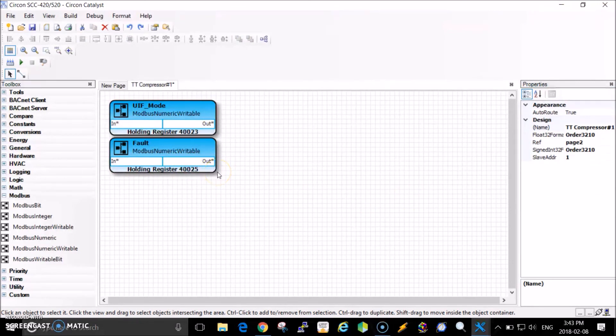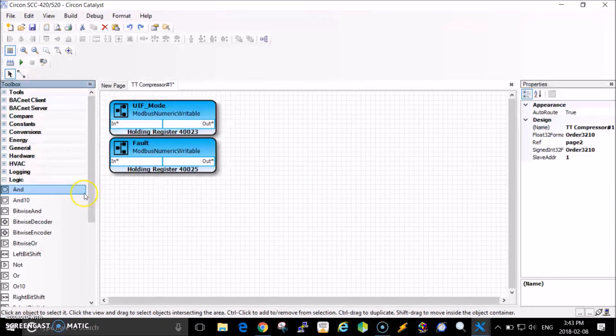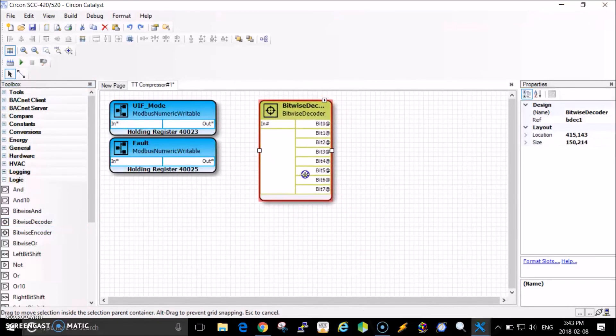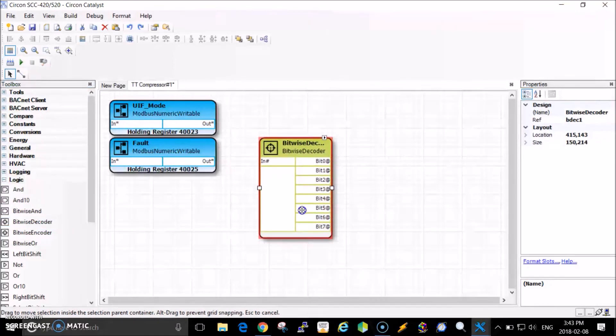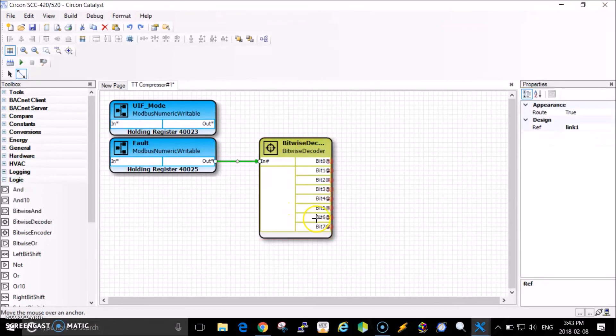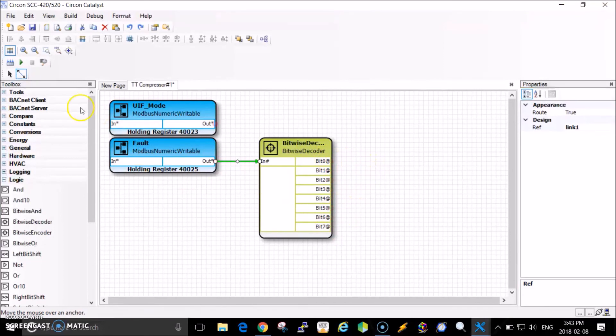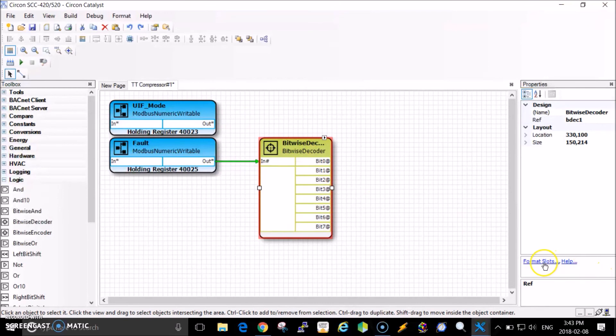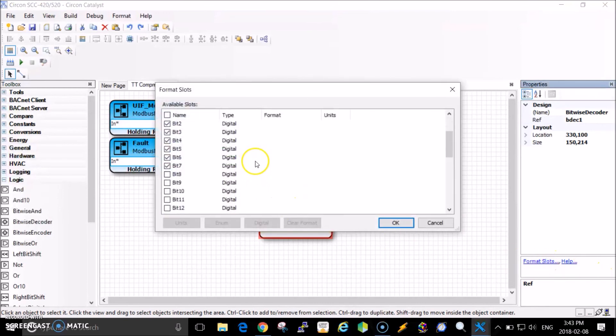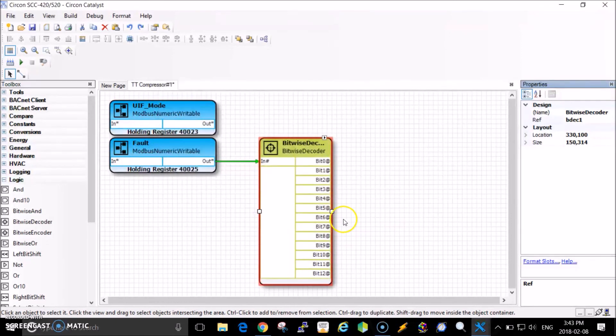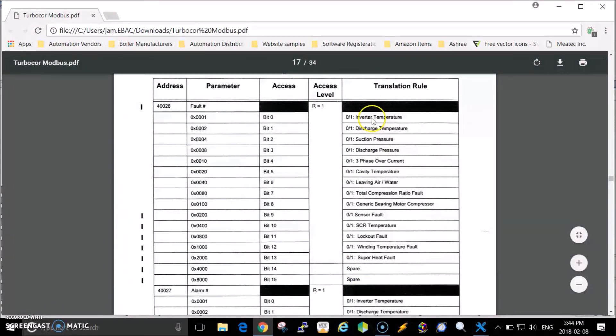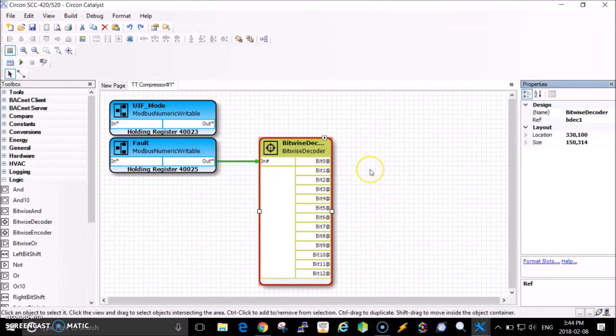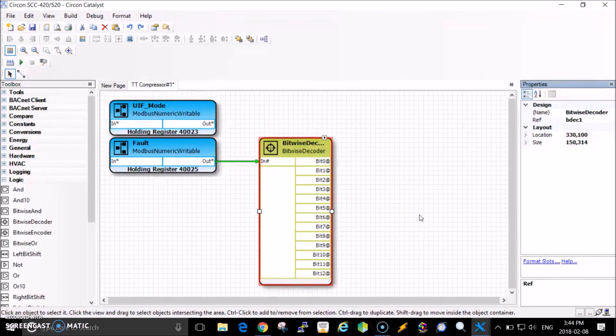This would read the whole number, but if I wanted to break out the bits, I would go in my Logic Function and there's a block called Bitwise Decoder. I can use this to expose the bits by themselves. I'll connect this to this, and then all these bits will be exposed as individual data to be used in the program. If that's not enough, you can go to Formats and increase more of the bits. Now I can see all these temperature alarms as individual pieces of data and use them in my Catalyst program.